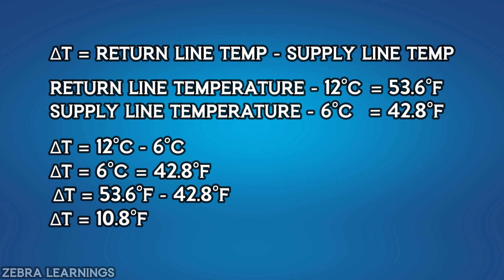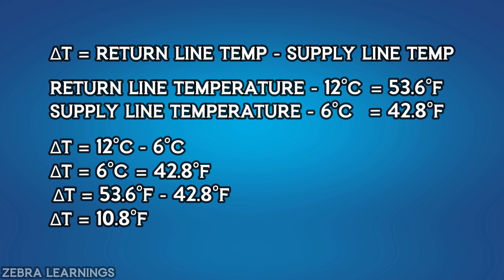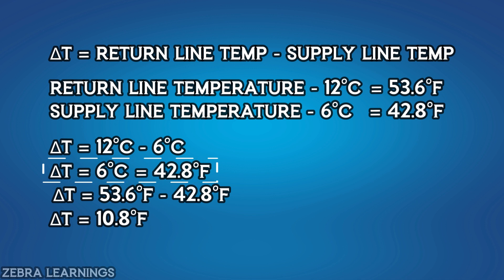When calculating in degrees Celsius, the delta T answer is 6 degrees Celsius, whose direct Fahrenheit conversion would be 42.8 degrees Fahrenheit. But calculating the difference directly in degree Fahrenheit gives 10.8 degrees Fahrenheit. So when working in degree Fahrenheit, we must convert both the return and supply temperatures to Fahrenheit first and then find the difference. If you find the difference in degree Celsius and then convert it to Fahrenheit, the answer will be wrong.